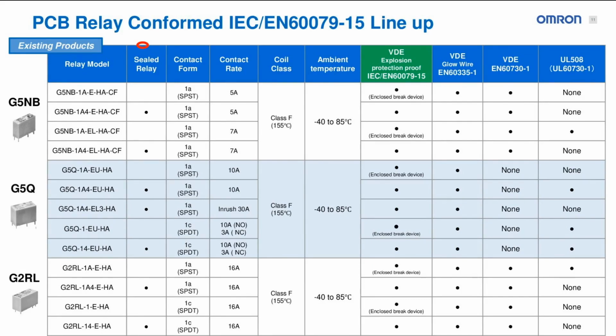We have various contact forms, and we have various contact ratings. For G5NB, we have one form A contact form only. We have 5 to 7 amp support. For G5Q, we have one form A and one form C contact forms, and we support 10 amps on the normally open contact, and for one form C, 3 amps on the normally closed.